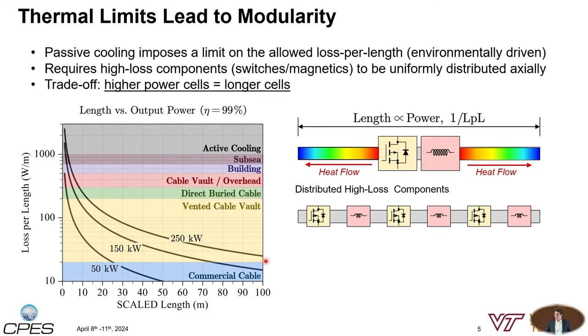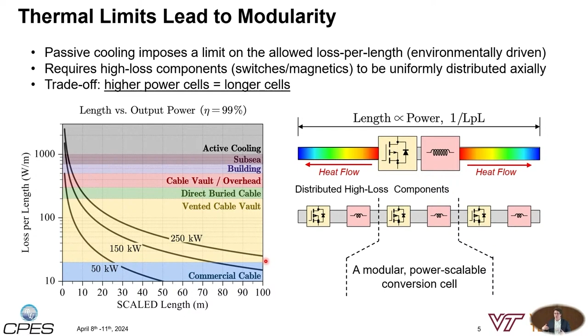This has implications for the topology, and it means it's not all about density. My highest loss components are my switches and inductors, and we may be inclined to pack them together as closely as we can for a dense form factor. But if I need to operate in an environment requiring a low loss per length, it doesn't matter how dense that is, I still need to stretch it out over 100 meters, so that density didn't really benefit you. What naturally falls out of this is a modular structure where we distribute these heat loads along the length of the cable, however long that needs to be. Once we distribute them, a modular nature falls out, with modular power converter cells that we stack end to end. Every time we add a cell, we increase our power, but we also increase our length, and so we break that barrier.